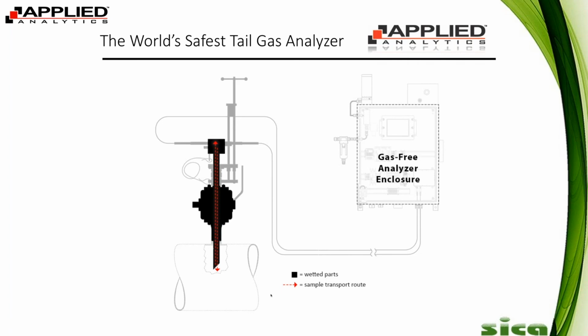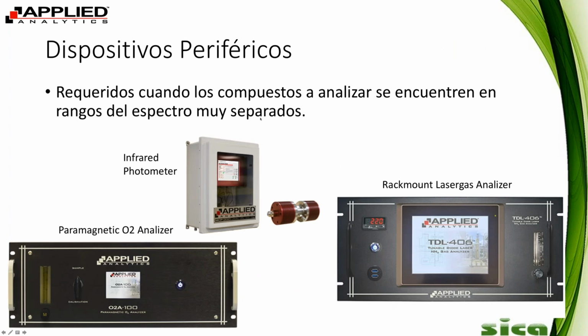Here I will briefly discuss our products that are not the OMA or the TDL. One of them is the infrared photometer, the IR photometer. What we do here is measure moisture, carbon dioxide, carbon monoxide, methane equivalency. Those are some common ones that we measure with the IR photometer. This allows us to have better bids on projects where, say, you want an H2S and a CO2 measurement. We can provide one analyzer to do those by adding the IR photometer into the sampling conditioning system of the OMA, or something along those lines.